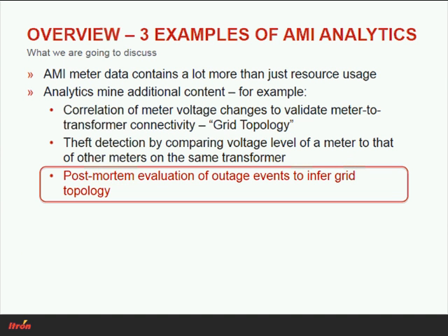We all know that when an outage occurs, AMI meters will transmit the power off signal, but especially in a mesh network, only a subset of those signals will actually make it to the central office, because some of the meters in the middle of the outage emitted their last gasp, but it will never make it because other meters that are supposed to retransmit are already without power as well. So inevitably, you have an incomplete picture of the meters affected by the outage.